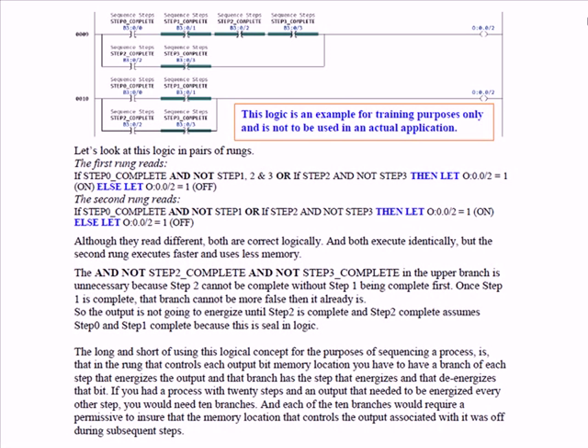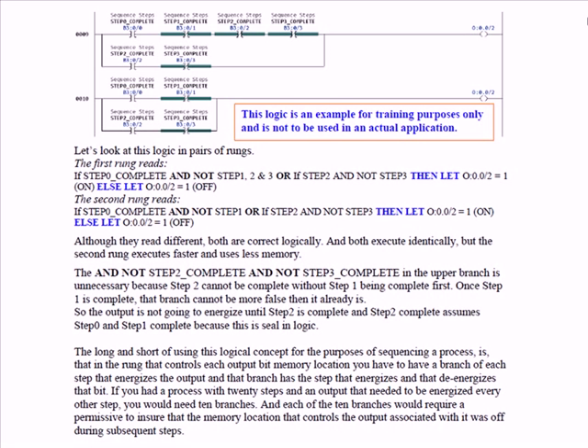Now if we look at the second rung, rung 10: when step 0 is complete, output 2 comes on. When step 1 is complete, that part of the rung goes false and output 2 goes off. When step 2 is complete but not step 3, output 2 comes back on. And then when step 3 is complete, both ladders, both ORed sets of permissives, are false and output 2 is de-energized.